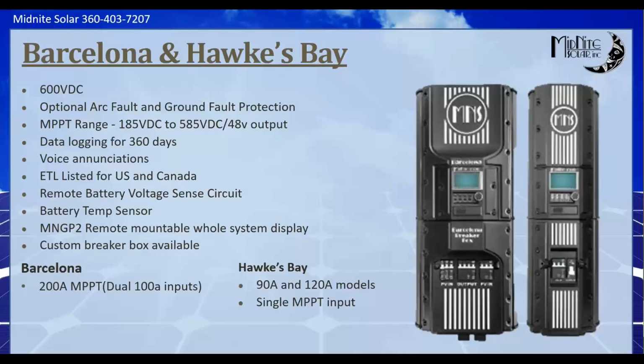MPPT range—this says the MPPT range, I've got to fix this slide, but it says it's 185 to 585. The unit will track down to about 200 volts. So in a perfect world, I would start out at 300 volts VOC as your minimum, 600 is your maximum—those are kind of your two numbers you're shooting for. The controller will run all the way to 600 volts; if it's at 601, it will not turn on.